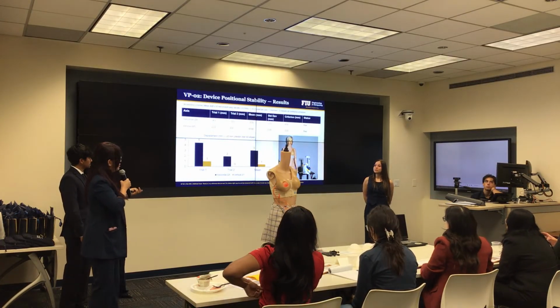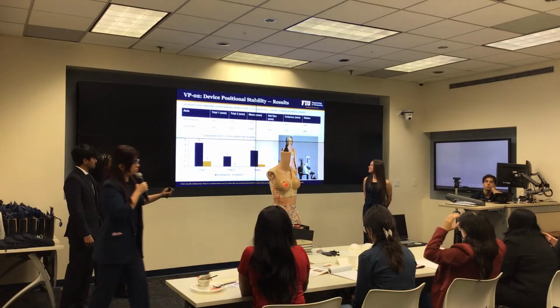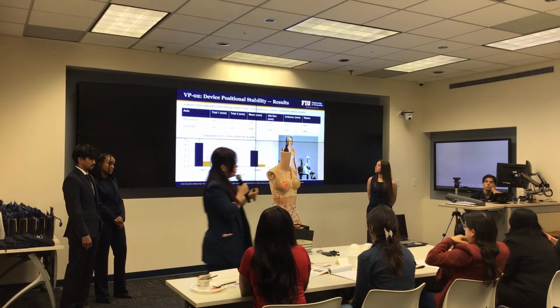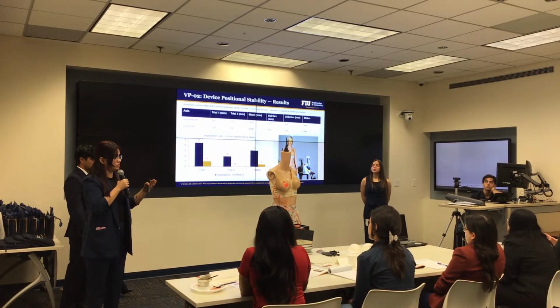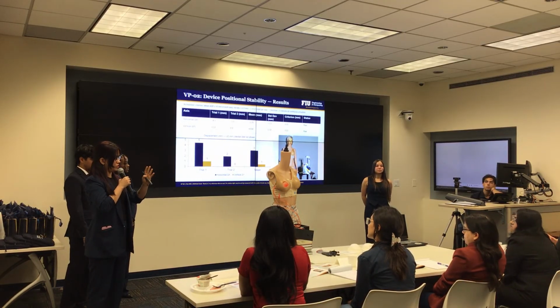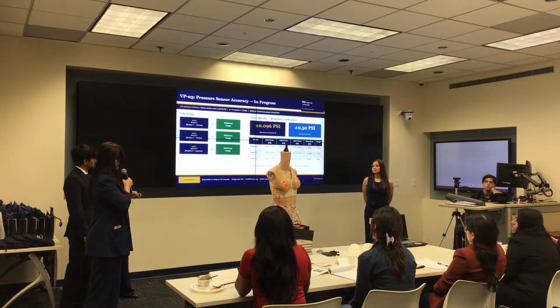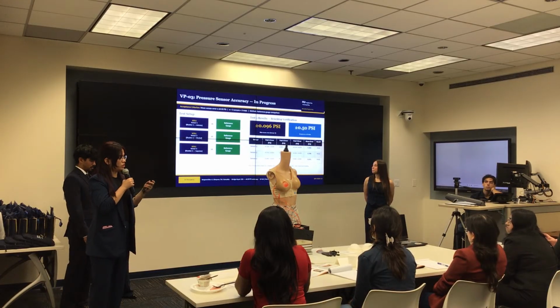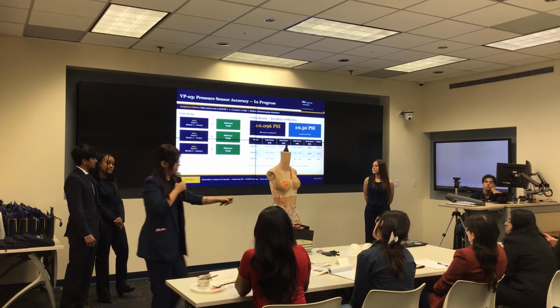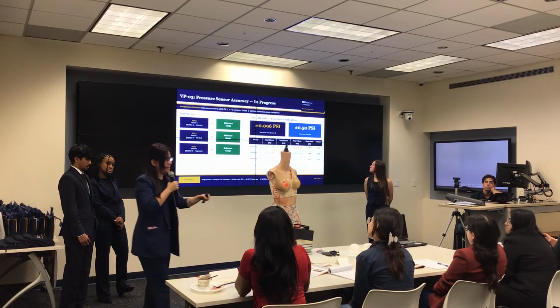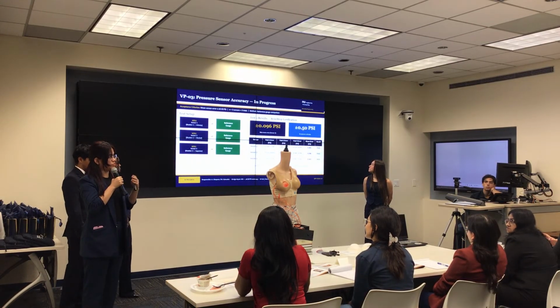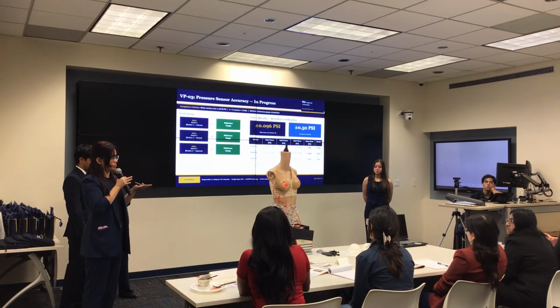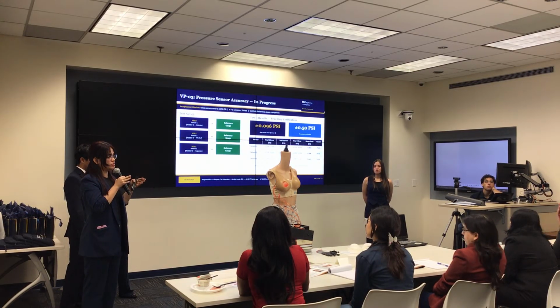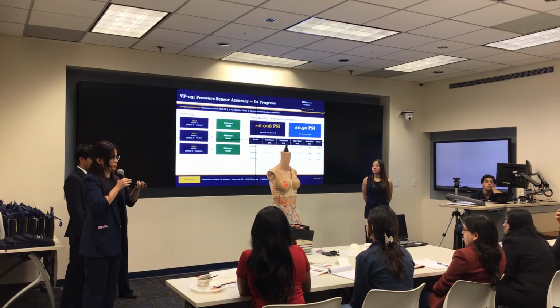For the longitudinal stability, we place a laser point in this area here, and we turn the machine on for 15 minutes and see how much the point moved from the middle. For the reference of the pump, we connect it to the pressure sensor, and we also connected it to another pump system to see what measurement it gave us on both of them. And we detected that the difference is very small, so what we read is actually the PSI that we need.